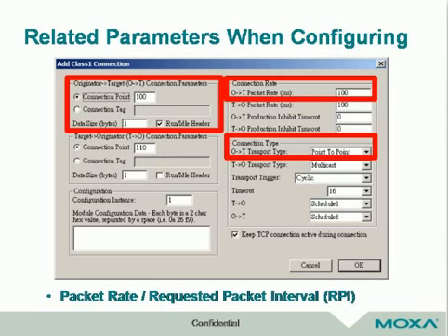The first one is connection point. As I mentioned before, in most cases, the EtherNetIP scanner read or write from the same object, the assembly object. But what part of the assembly object? The address or attributes could be very different for devices from different vendors. For example, our MGate 5105 is at 100 for output O to T, 110 for input T2O. User can find this information in the user manual of the device.